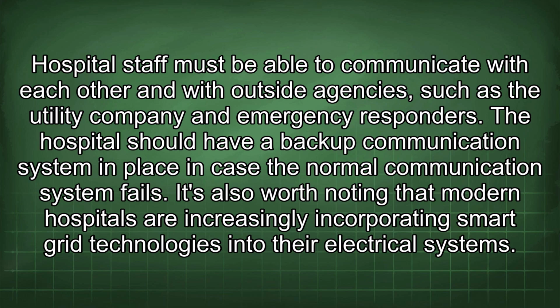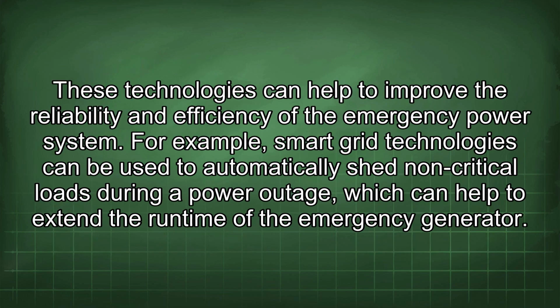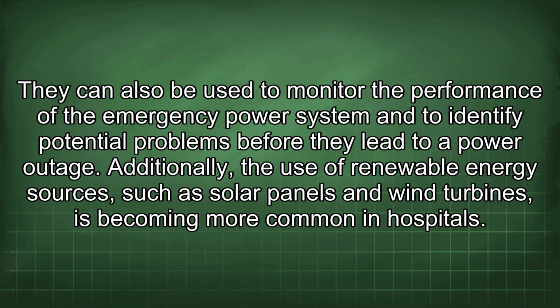It's also worth noting that modern hospitals are increasingly incorporating smart grid technologies into their electrical systems. These technologies can help to improve the reliability and efficiency of the emergency power system. For example, smart grid technologies can be used to automatically shed non-critical loads during a power outage, which can help to extend the runtime of the emergency generator. They can also be used to monitor the performance of the emergency power system and to identify potential problems before they lead to a power outage.